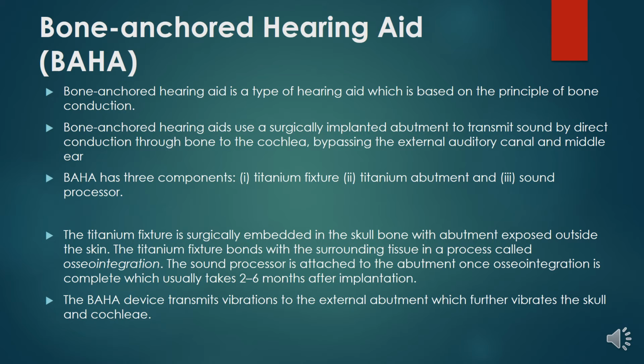Now the titanium fixture is surgically embedded in the skull bone with the abutment exposed outside the skin. The titanium fixture bonds with the surrounding tissue in a process known as osteointegration, and the sound processor is attached to the abutment once osteointegration is completed, which usually takes 2 to 3 months after the implantation. And the BAHA transmits vibration to the external abutment, which further vibrates the skull and the cochlea.